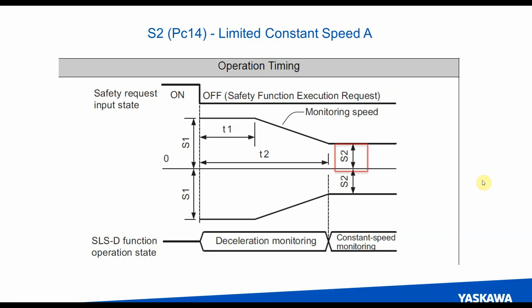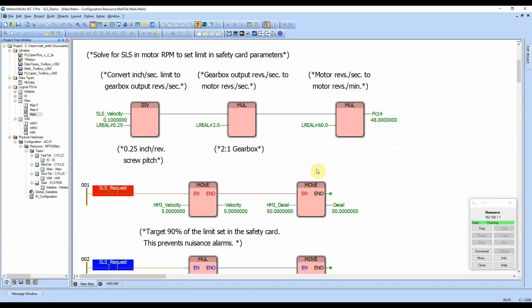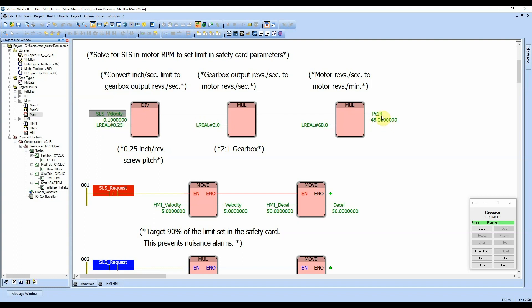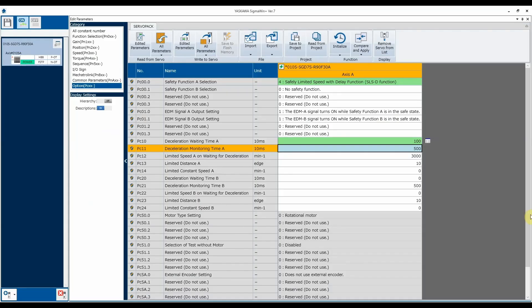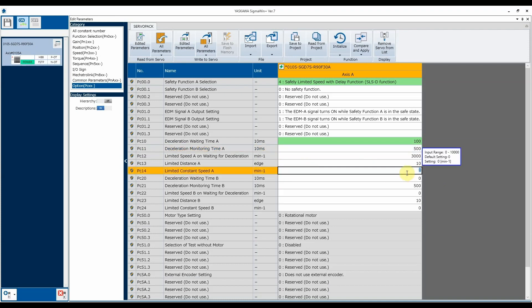And then the last one is the velocity or speed that we need to be at once that time is elapsed. So if the motor exceeds that, then it'll be disabled. We want to know how to set that for our machine. It's going to depend on the mechanics that are tied to the motor. I've set up a little demo program in MotionWorks IEC to implement a machine configuration. In my machine, my safe limited velocity or safe limited speed is going to be set to 0.1 inches per second. And then we need to convert that from inches per second on the machine to motor RPM. This calculation here is running through and that solves it for 48 RPM. So if we go back to Sigma Win Plus, our safe limited constant speed that we're always gonna be looking at is gonna be 48 RPM.